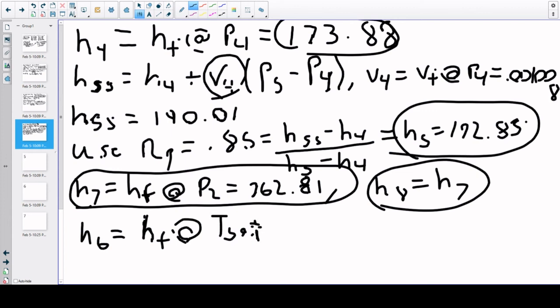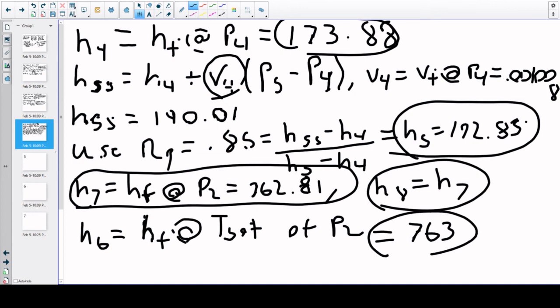Because of the properties of heat exchangers, when you're exchanging heat, the temperature of the fluid going towards the boiler cannot get hotter than the saturation temperature of the water heating it, right? So if you have a 40 degree water that's giving heat to 20 degree water, the 20 degree water cannot become like 80 degrees without some extra help being put in.